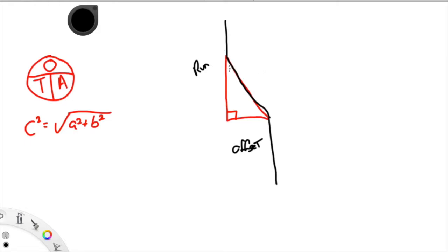So the way our fittings are measured in degrees is from the backside or the heel of our fittings. This line being a continuous 180 degrees, we want to know how far off of 180 degrees this fitting needs to be, and whatever that is, the same will be true over here. Come off of 180 degrees by 30, then you have to go back to 180 degrees by 30.